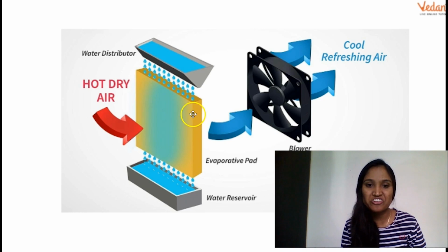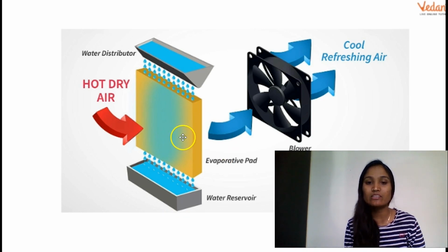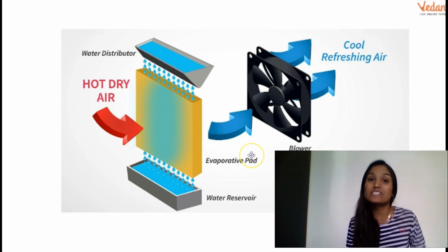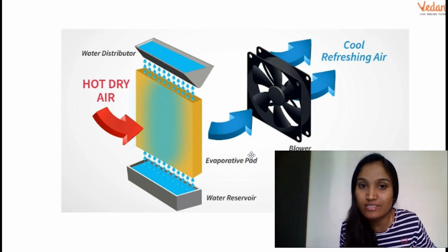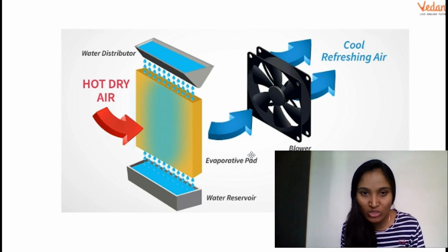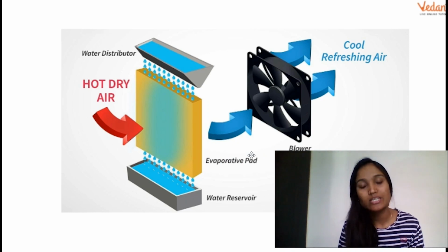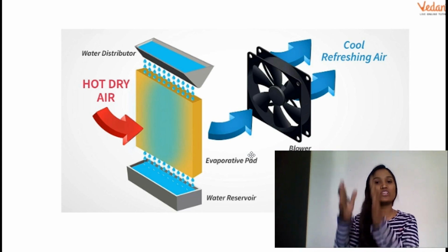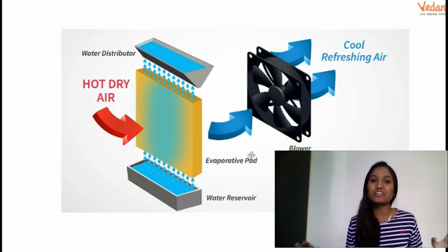So the water streams are absorbing energy and the air which passes through the water stream is now no more hot, because it already gave its hotness, its temperature, to the water pads, right? Are you all able to follow? Yes, that's great. So now what is happening? The temperature of air is being reduced. So the air which comes out of these water streams is cool and refreshing.